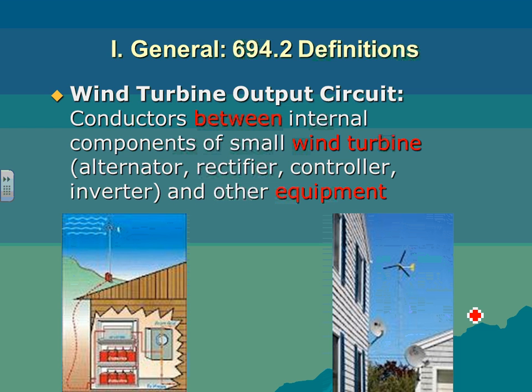So what they use is an induction generator. The relationship between the speed of the alternator and the frequency allows you to fluctuate so much and maintain the same frequency. So they use a dual-fed induction generator, and this is where they use the grid to actually start that turbine. The alternator, it's interesting, the technology that they use: inverter, converter, bidirectional. In one direction, they use the grid to start and control the speed of the induction generator and bring it up to speed. And when it's up and running, it starts pumping current. So they utilize power from the grid to start the alternator and then bring the power back into the grid.